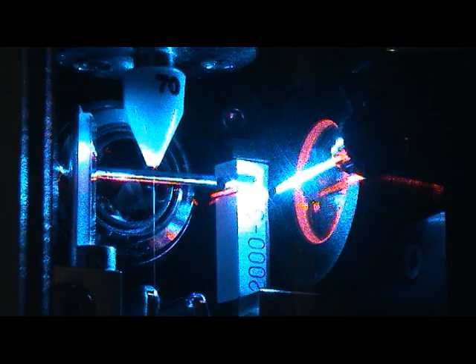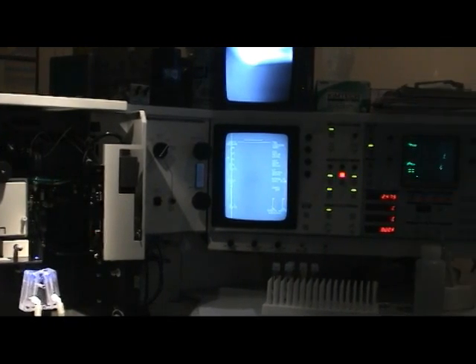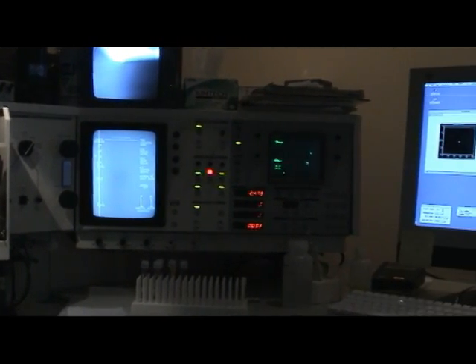Light scattered to the side is collected through a microscope objective lens and sent down an elaborate pathway of optical filters, beam splitters, and eventually the signal is sent to photomultiplier tubes. We're really just gathering light from cells in order to generate an electronic pulse that's converted into readable data, and that data is analyzed by software.